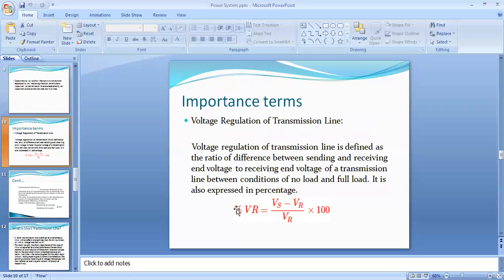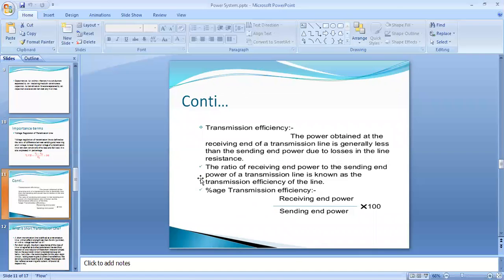Important terms: voltage regulation and transmission efficiency. Voltage regulation is defined as the ratio of the difference between sending-end and receiving-end voltage to the receiving-end voltage, expressed as a percentage: (Vs − Vr) / Vr × 100. Transmission efficiency is the ratio of receiving-end power to sending-end power, expressed as a percentage: (Pr / Ps) × 100.